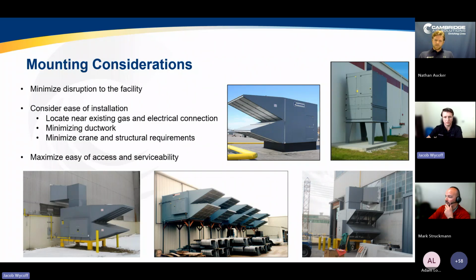This can reduce the amount of gas piping and electrical you need to run, and lower the install cost. You want to minimize the ductwork. So you want to locate the unit near where would be a good place to immediately discharge the air into the space. This is going to save you some money on ductwork, and it's also going to reduce the impact of ductwork on the facility, as you no longer have to worry about forklifts hitting that ductwork or interference from some overhead cranes that might be happening in there.